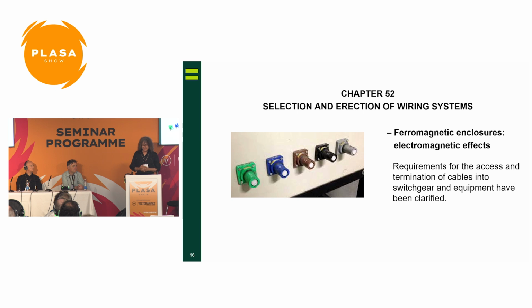Next thing I want to look at is ferromagnetic enclosures. You'll be familiar that where you have cables going into a ferrous enclosure, if they don't go through the same window or opening, you can get eddy currents flowing which can lead to overheating. What's gone into BS 7671 this time is: if you're up to 200 amps, there's not really a lot to worry about. If you're going over 200 amps and through different windows of entry, it's a discussion with the owner or manufacturer of the equipment to make sure they're happy with the heating effects that could occur.